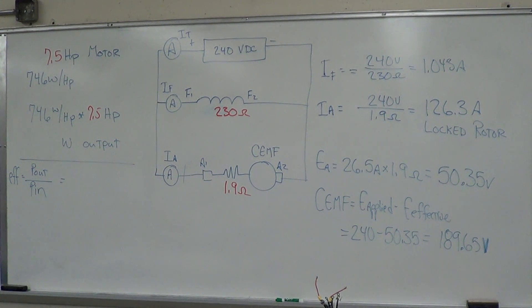Now you said the locked rotor current is the same thing as inrush current. That's your inrush current. It's the amount of current that will inrush into it until it starts turning. The moment it starts turning, you'll have some counter-EMF developed.